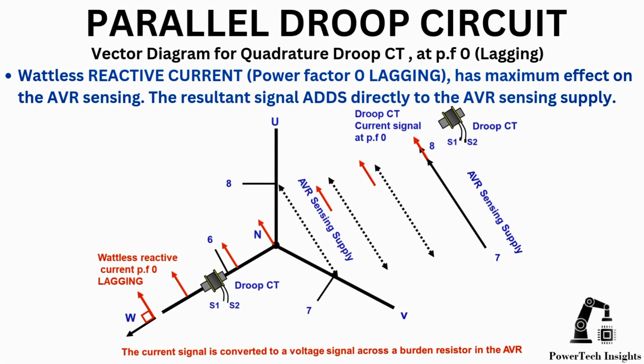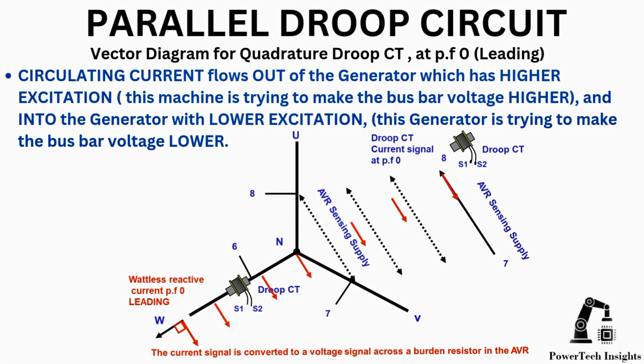This is the vector diagram for quadrature droop CT at power factor 0, lagging. Reactive current at power factor 0 lagging has maximum effect on the AVR sensing. The resultant signal adds directly to the AVR sensing supply. This is the vector diagram for quadrature droop CT at power factor 0, leading. Circulating current flows out of the generator with higher excitation — this machine is trying to make the bus bar voltage higher — and into the generator with lower excitation, which is trying to make the bus bar voltage lower.